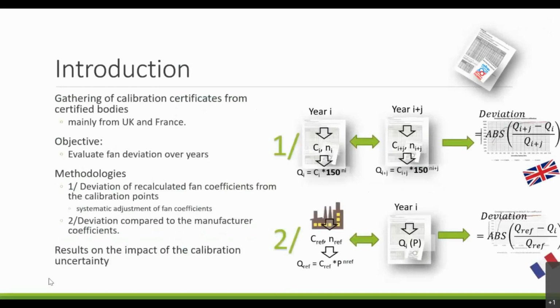So, our objective here was to evaluate fan deviations over years to know which calibration requirement should be put on blower-door fans. To do that, we have gathered calibration certificates from certified bodies, mainly from the UK and France, where the calibration is mandatory every year in the UK and every 2 years in France. And with those calibration certificates, we have evaluated the deviation of the blower-door fans.